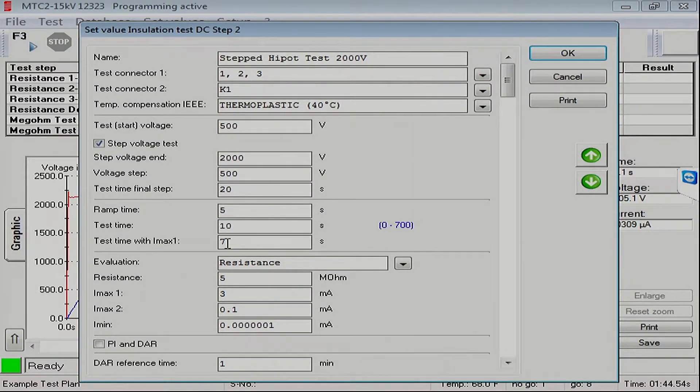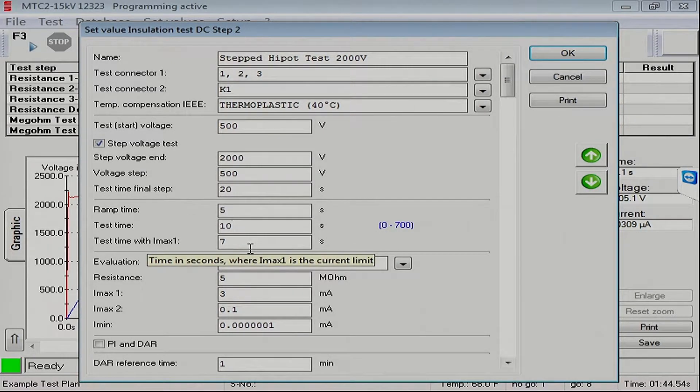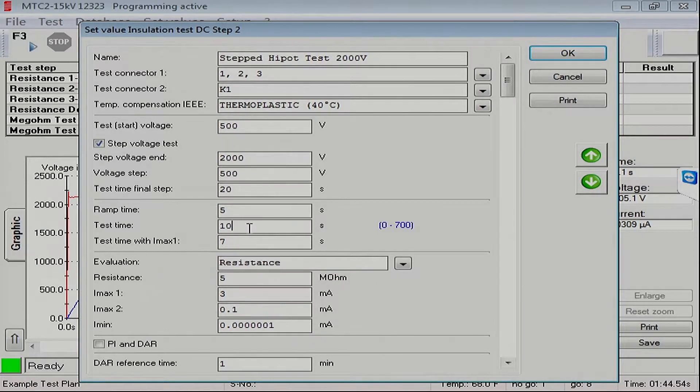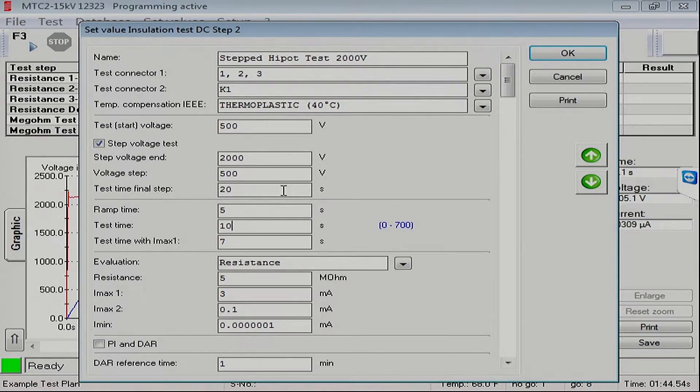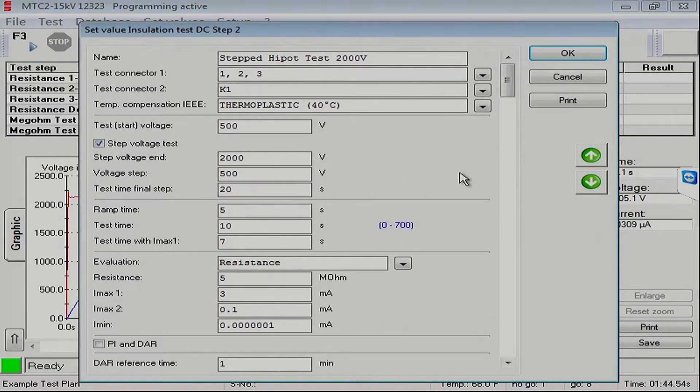Okay, so we're going to ramp up for five seconds, hold in the coarse current range for seven seconds, and we'll test for 10 seconds, and we'll go up in 500 volt steps. The last step we will hold for 20 seconds. And that should be all we've got to do.